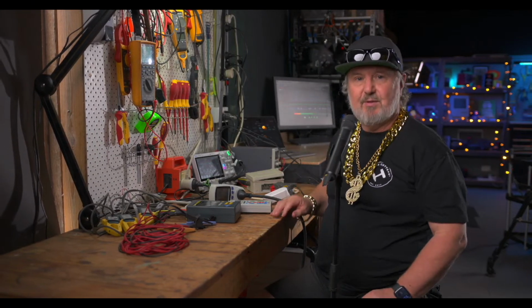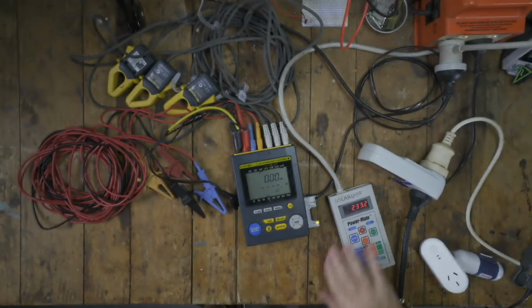But you can do some things yourself. One is about when the generation goes to the grid - so putting in batteries, for instance. Another, about installation, is when installing an inverter system, if you can locate it as close as practicable to the point of coupling with the grid - because the longer your submains are, the greater the voltage rise. There's actually regulations around that in our Grid Connect standard 4777 Part 1, which tells us the maximum voltage rise across two segments: the inverter to main switchboard, and main switchboard to the point of common coupling - typically where your mains box is or where your connection to the poles and wires in the street are. So that's two devices, but there's a third one, which is more a professional tool.